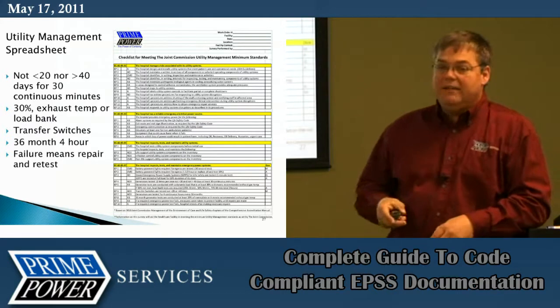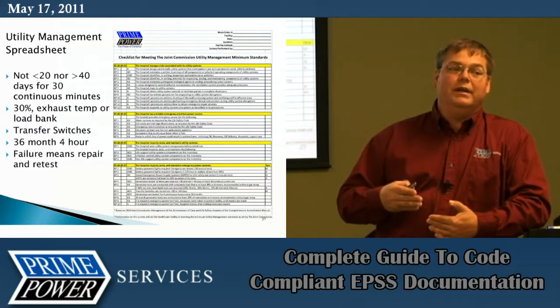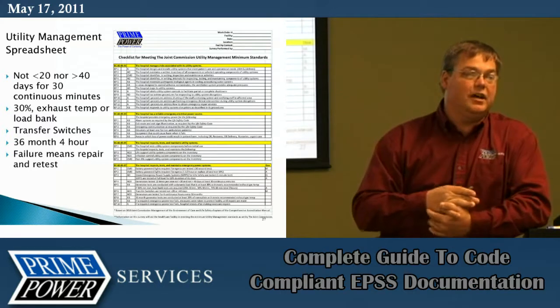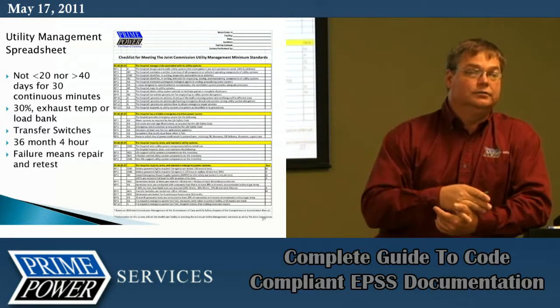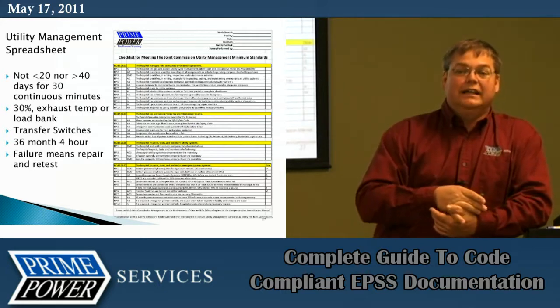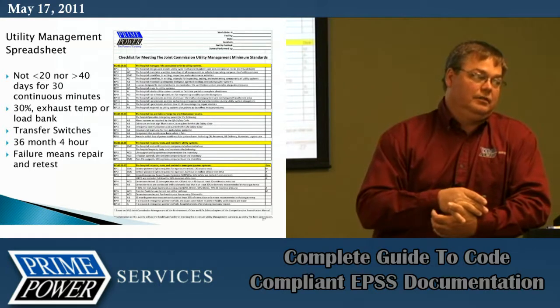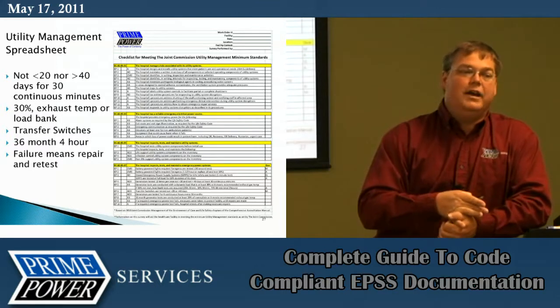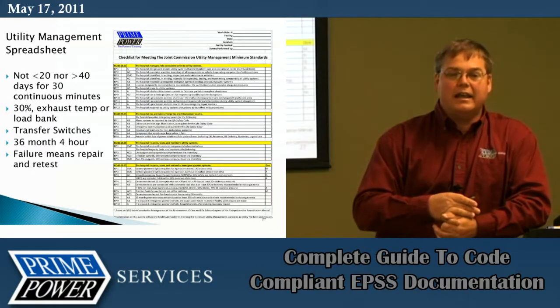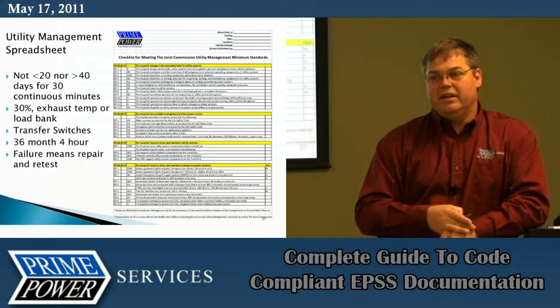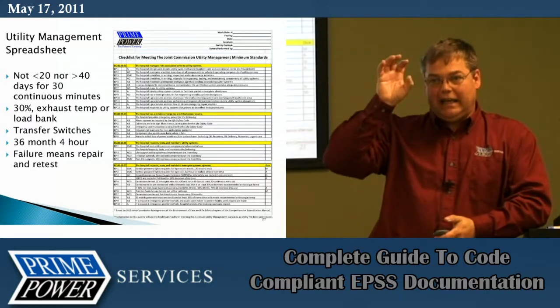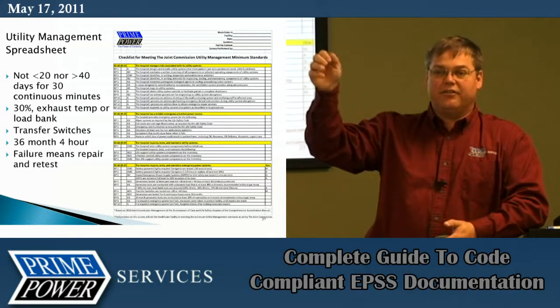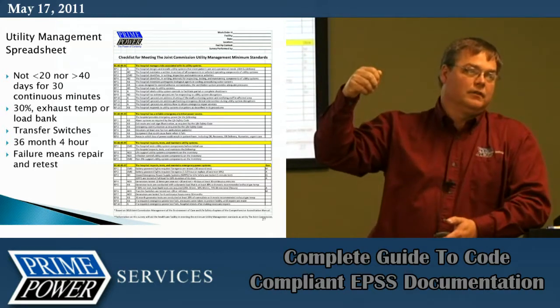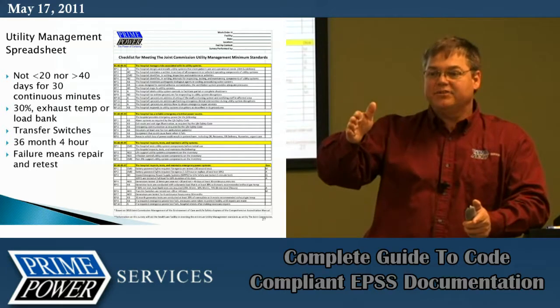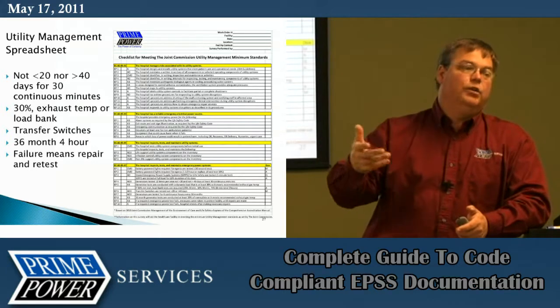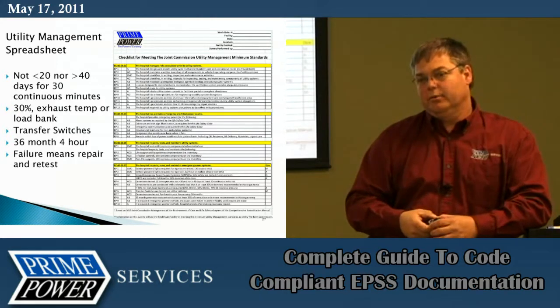Same thing occurs - you must run it at 30% or meet the exhaust gas temperature. Chris read the standard a few minutes ago; that's the exact standard Joint Commission follows. If you can't run it at 30%, can you make exhaust gas temperature? We were talking earlier about how you measure that - there's a lot of specifics on that. It's not a good, reliable resource to check your engine by unless you have a temperature gauge in the correct place. Using a laser thermometer will not give you an accurate reading. There are specifics on where that temperature monitoring has to be, and if you don't have that capability, I wouldn't recommend using exhaust gas temperature as your monitoring point.